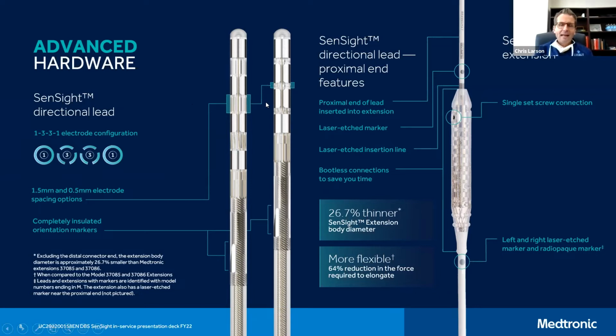And when we're getting that excellent control of tremor or rigidity or whatever it is, we're inadvertently having to stimulate motor function or motor fibers, and we're creating some facial contractions or some double vision. And so we're limited in getting that. With the directional component of this, now we can selectively stimulate in one direction and really ramp up the stimulation, get a better overall benefit. And at the same time, we're reducing our side effects by not stimulating the area that we don't want to stimulate, where there are important structures.